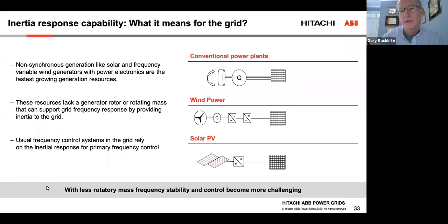So wind connects to the grid through a back-to-back power conversion process. From the generator, it's converted from AC to DC, and then inverted back again to AC, this time at 60 hertz or grid frequency. Solar PV is similar, except you don't have the back-to-back, you're just taking DC from the solar panels and inverting that to 60 hertz AC for interconnection to the grid.